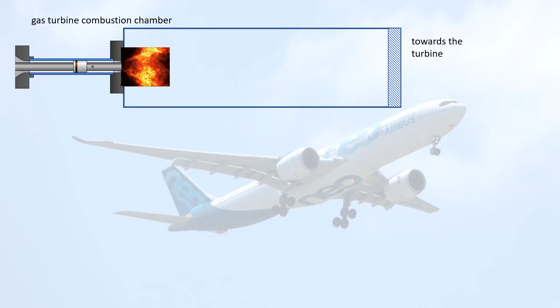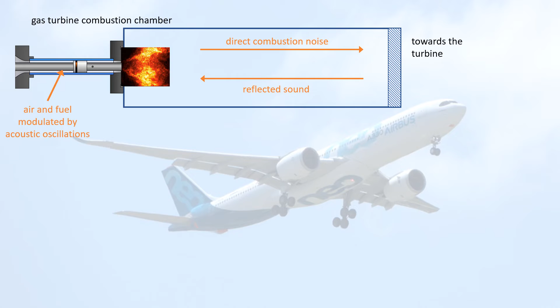Here you see a simplified cut of a gas turbine combustion chamber. In this chamber, the flame acts as a source of sound. The sound is reflected back towards the flame and modulates the incoming amount of air and fuel, which in return modulates the combustion noise. The loop is closed and can be unstable. An initial perturbation can grow after each cycle, leading to high amplitude acoustic pressure oscillation and large flame displacement that can damage the engine.